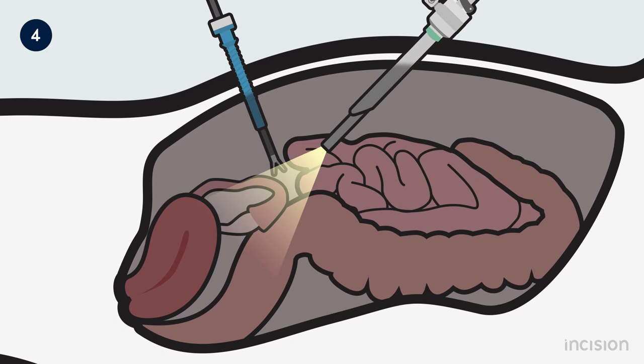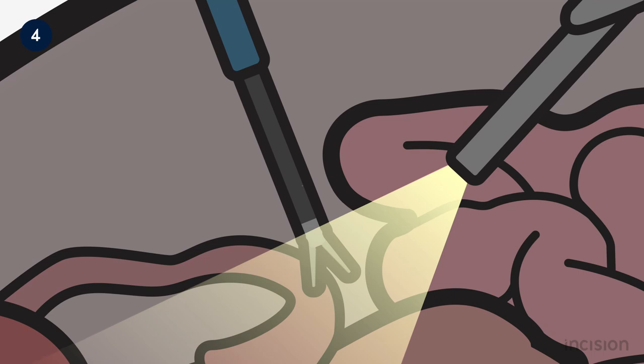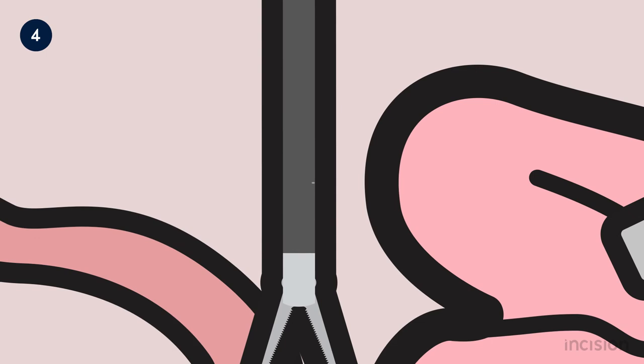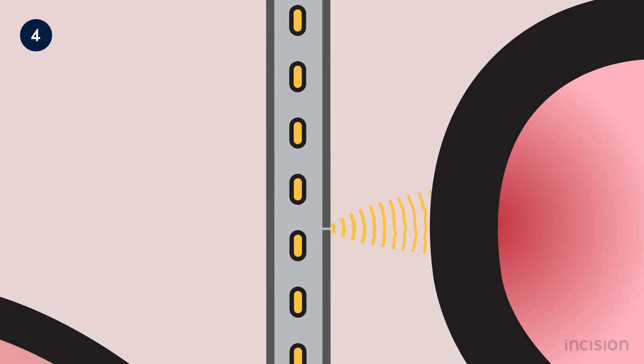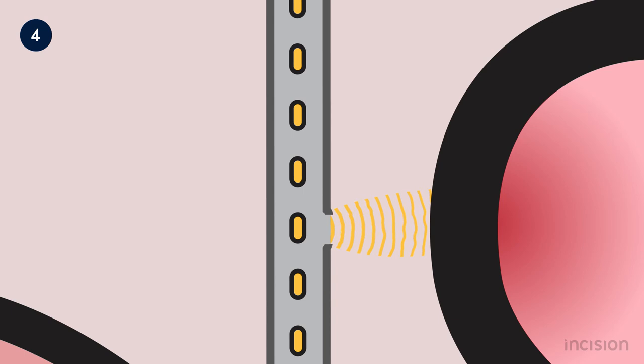Another complication whose chance of occurring can be reduced by using a low voltage is insulation failure. It may happen that the electric insulation surrounding the conductive core of a hand-held electrode is damaged. A microscopic scratch or hole in the insulation can be enough to allow an alternative pathway to form. During activation, the high current density at this location can burn both tissues and the remaining insulation. Often, this location is outside of the operator's field of view, and thus it can take a long time before burns are noticed.